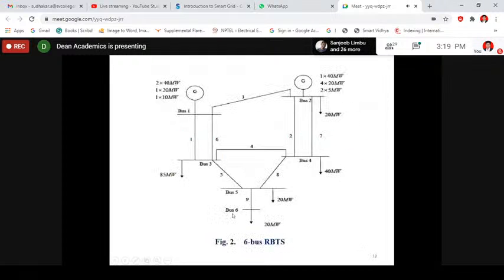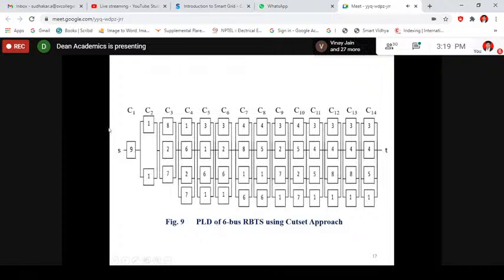First, unit 6 is getting isolated. This is called a cut set having one element only. So identify the cut sets like that. For load point 6, these are the number of cut sets, 14 cut sets in total, because that is at the fag end of the radial distribution network.